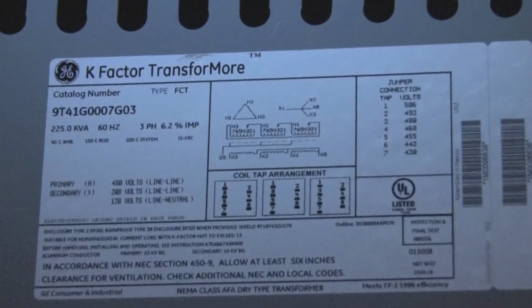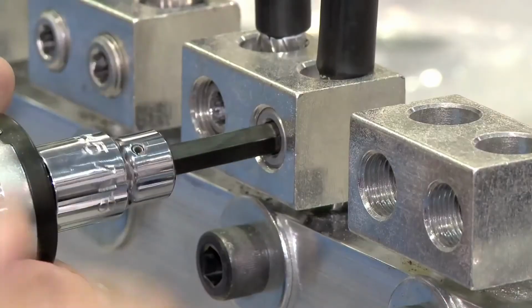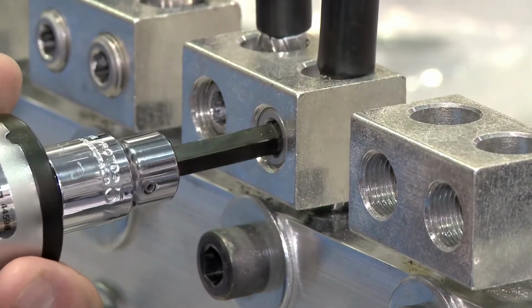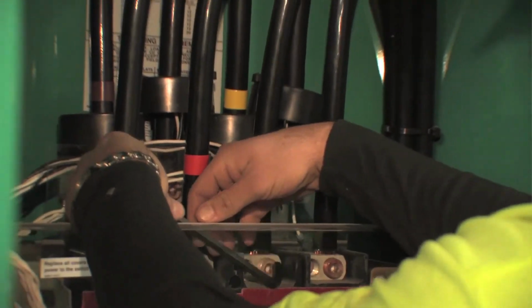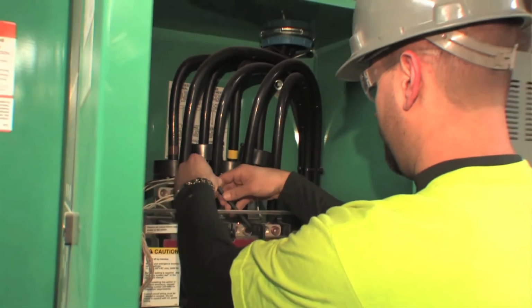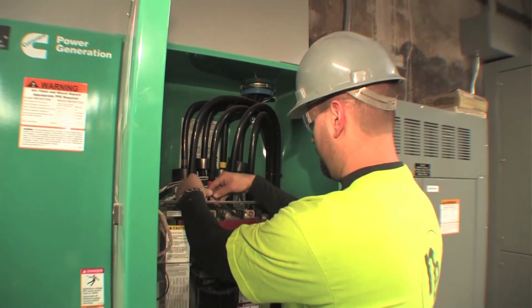At a previous company I was at, we had aluminum power feeds, and the biggest challenge we had there were the lugs would come loose on a very frequent basis. So to overcome that, we enlisted a local engineering firm who came in, reviewed everything, made the recommendation to go to copper. Once we did, we eliminated a lot of the frequencies of having electricians coming out all the time to check lugs, and also ensured ourselves that we had reliability from that copper for our power delivery.